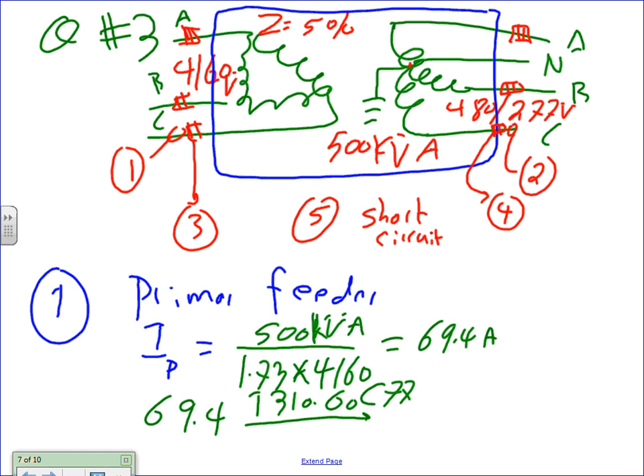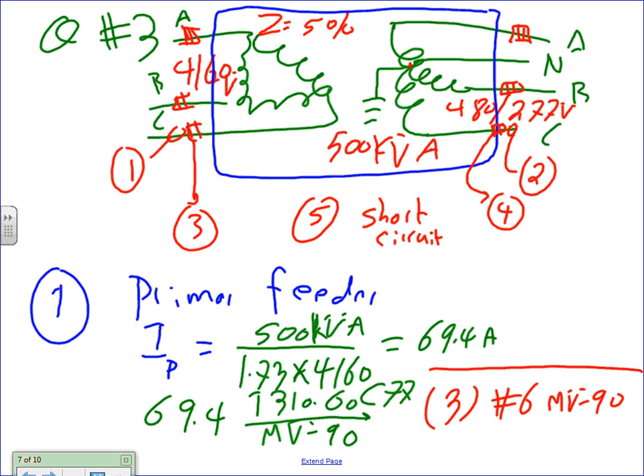That's a table that we're going to go to under which column? We're going to go under MV90, the medium voltage 90. If you guys go under this table, because it's medium voltage, you're going to find the three conductors. I need three conductors. Each one of them, the size would be number 6, and the type is MV-90, insulation medium voltage 90. So we go to a different table, Table 310.60(C)(77), under MV90, the most common.